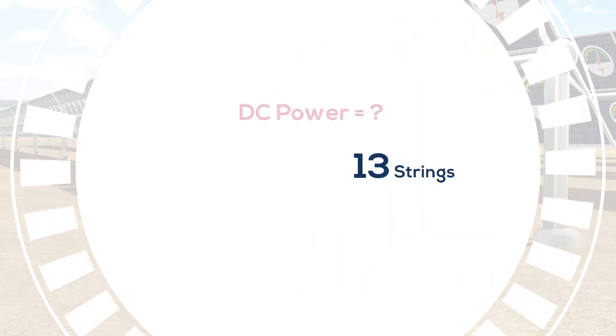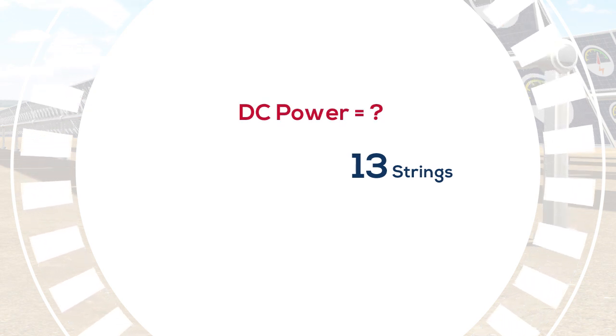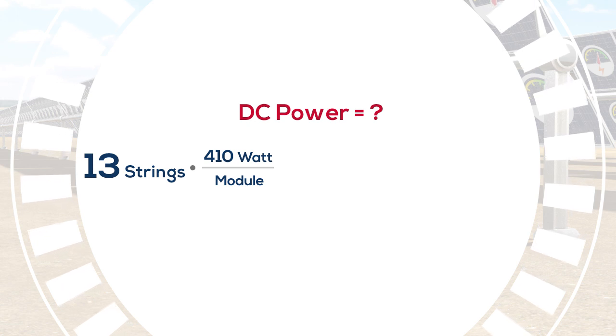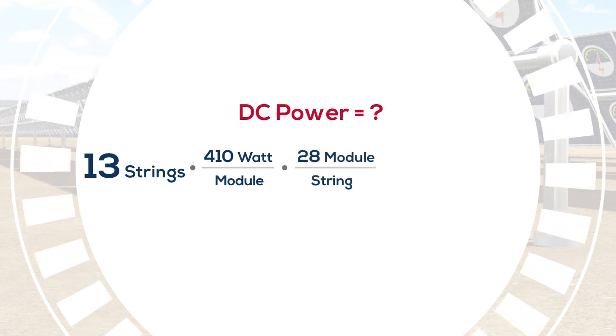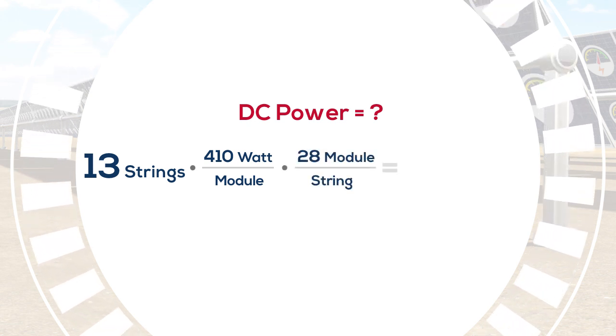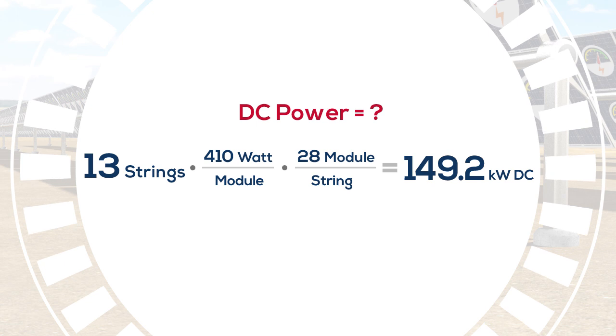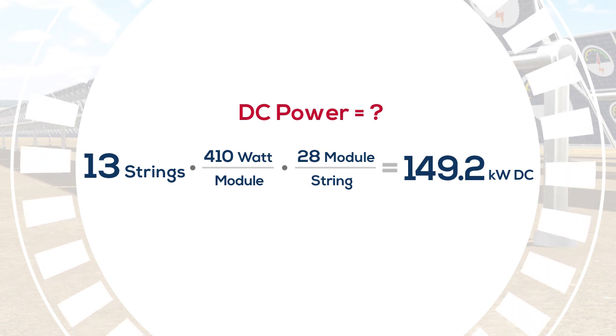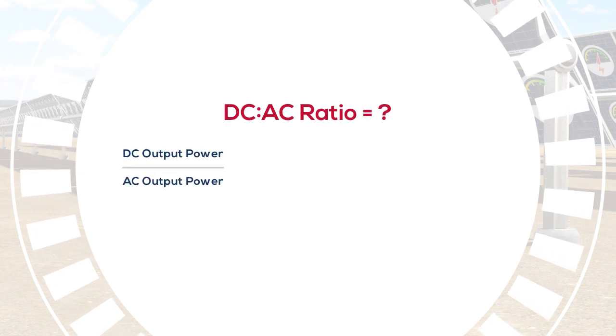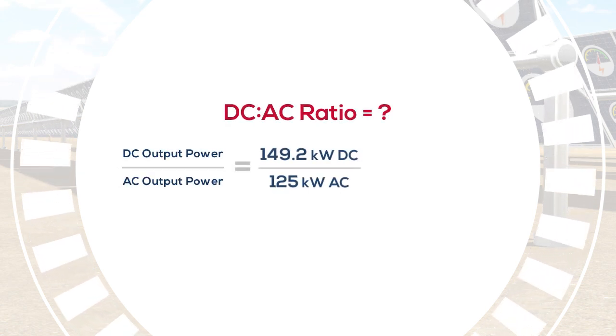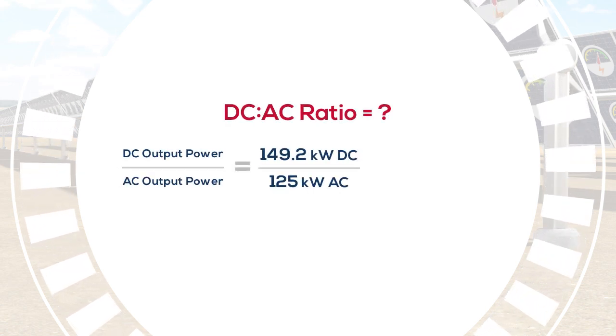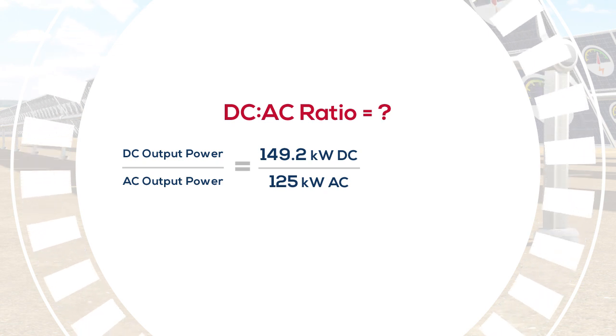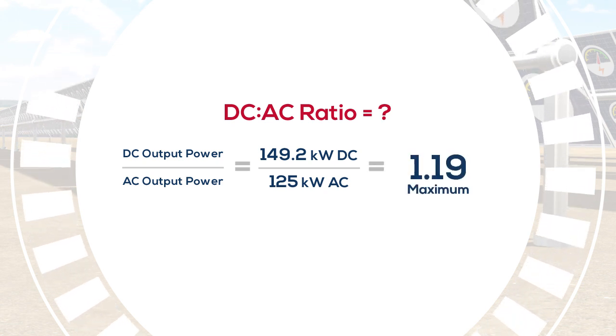The second step is to calculate the DC power, which is 13 strings times 410 watts per module times 28 modules per string, which yields 149.2 kilowatts DC of PV power to each inverter. The final step is to calculate the ratio of DC power to AC power, which is 149.2 kilowatts DC divided by 125 kilowatts AC, or 1.19 maximum.